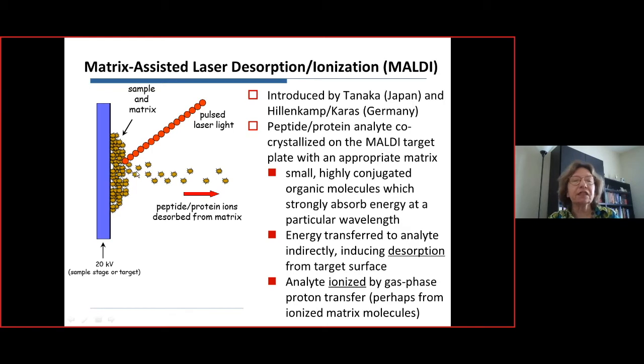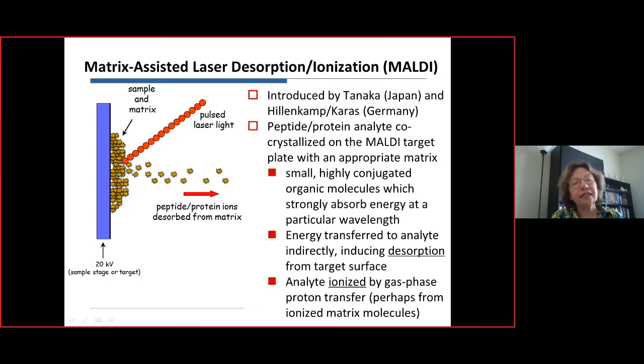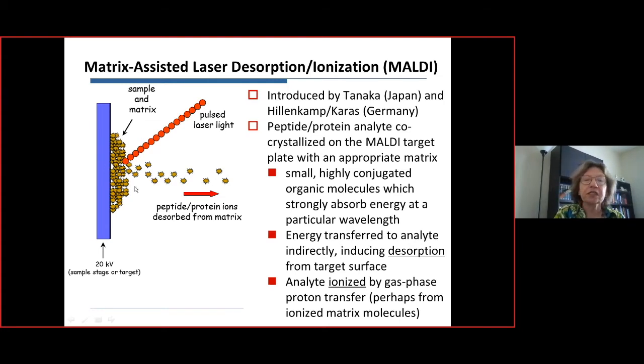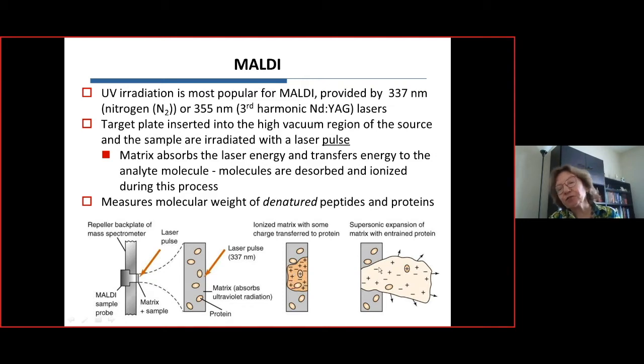Within this expanding plume, molecules are ionized — protonated in positive ion mode and deprotonated in negative ion mode — for peptides, proteins, and oligonucleotides. Once ionized, the analyte sees an electric field of ~20,000 V on the sample stage and is accelerated into the mass spectrometer. Cartoons illustrate a few analyte molecules dispersed in matrix and the eruption event from laser irradiation.